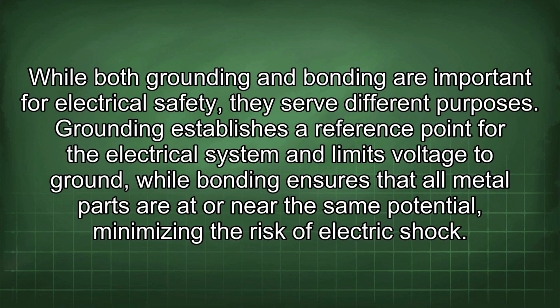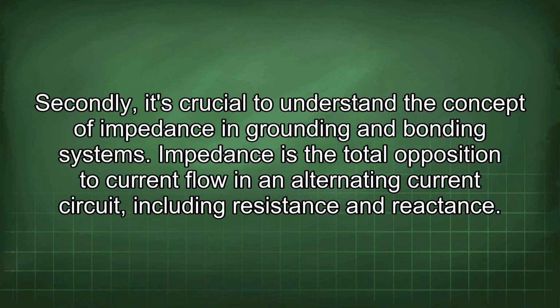Grounding establishes a reference point for the electrical system and limits voltage to ground, while bonding ensures that all metal parts are at or near the same potential, minimizing the risk of electric shock. Secondly, it's crucial to understand the concept of impedance in grounding and bonding systems. Impedance is the total opposition to current flow in an alternating current circuit, including resistance and reactance.